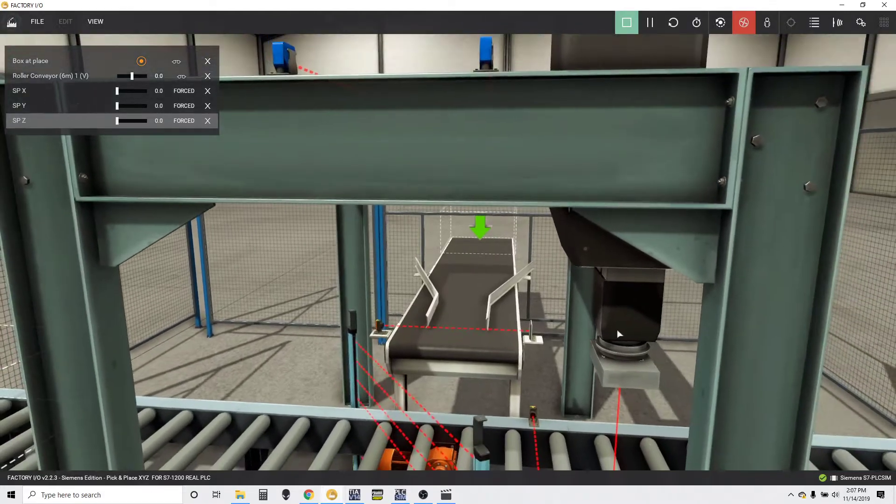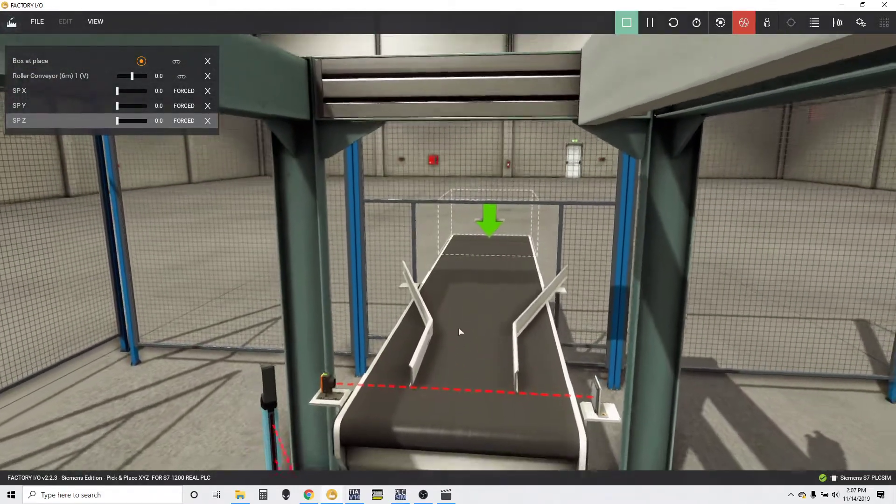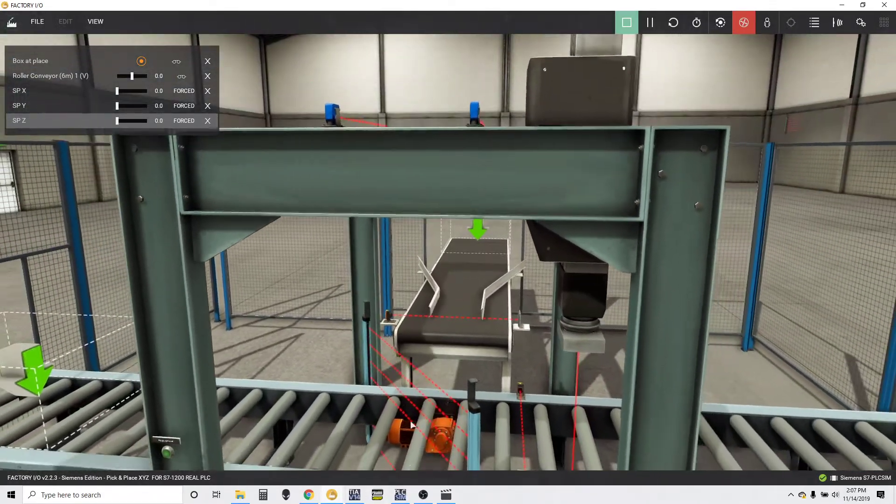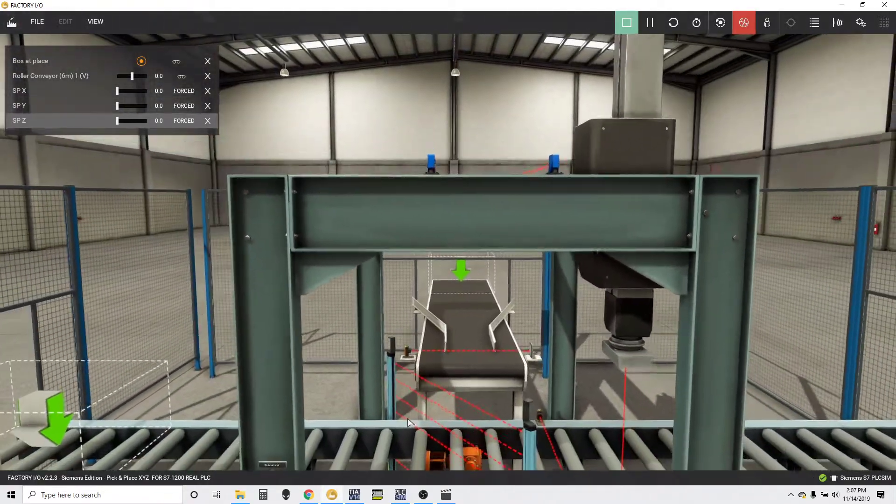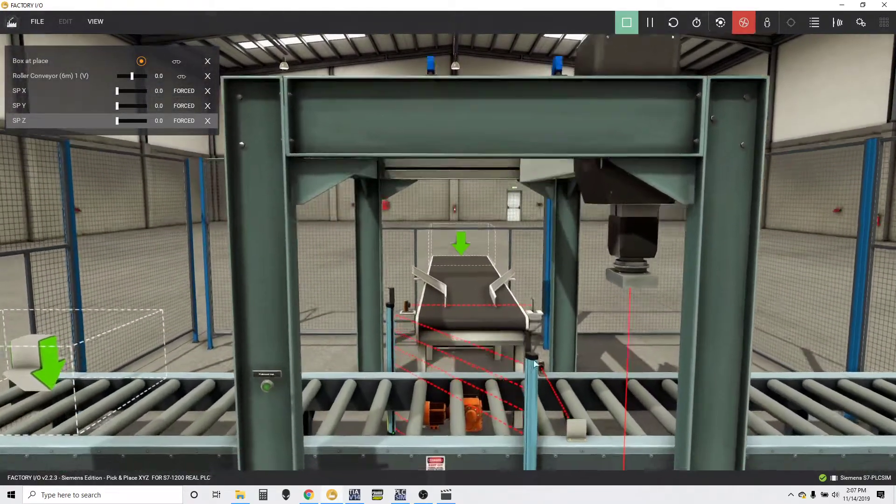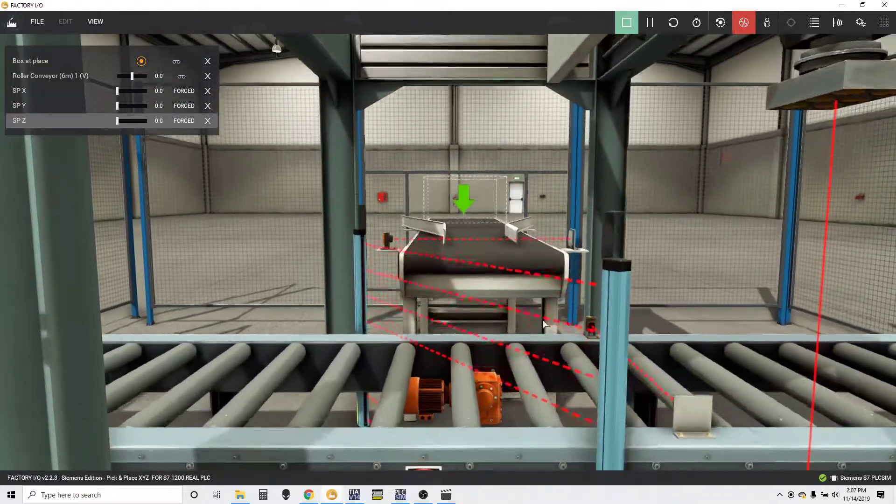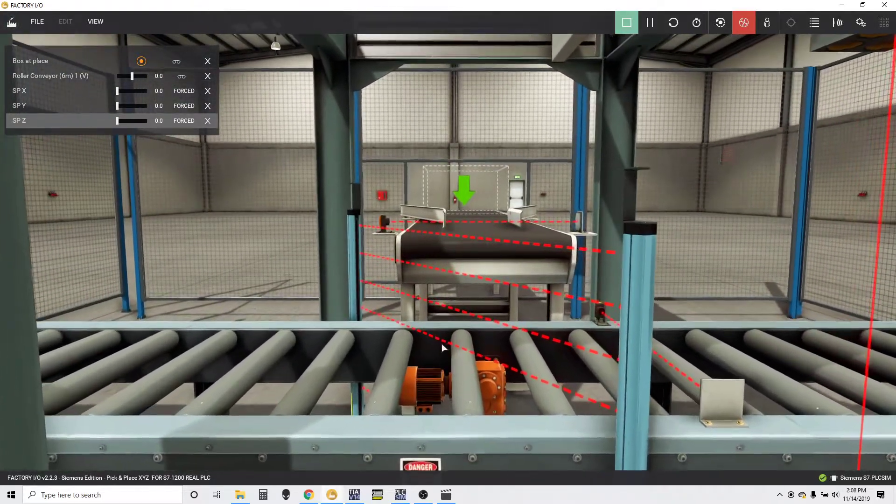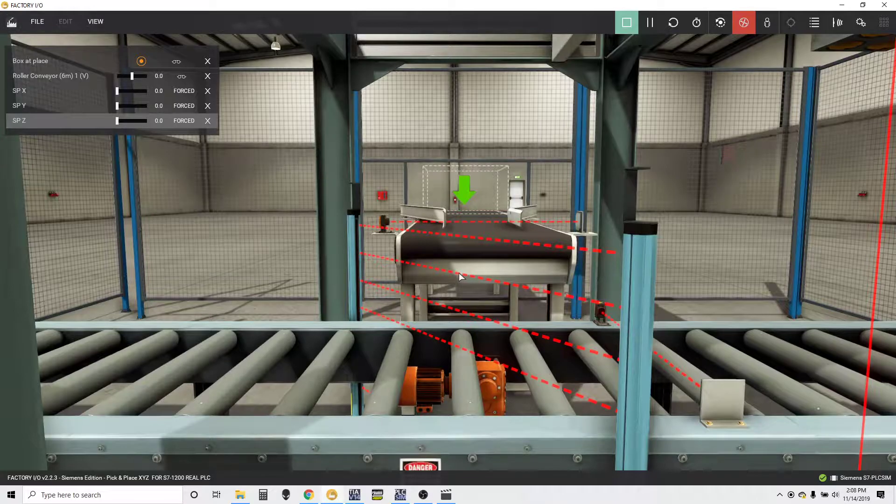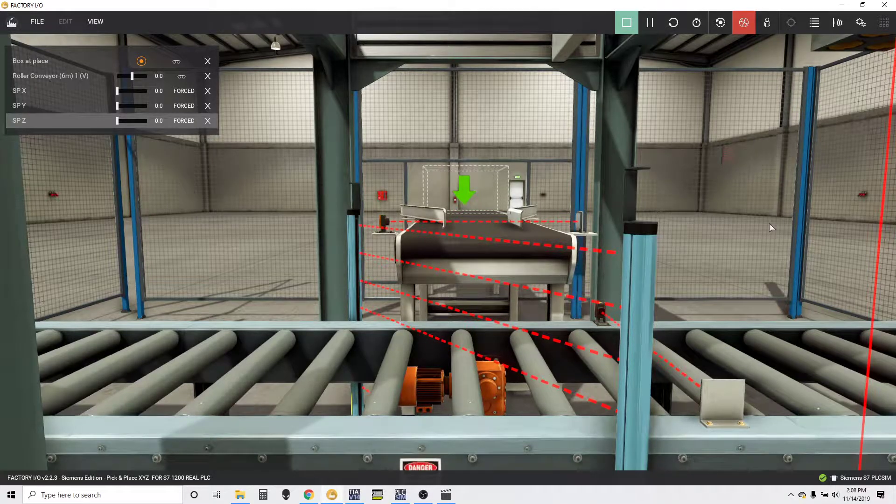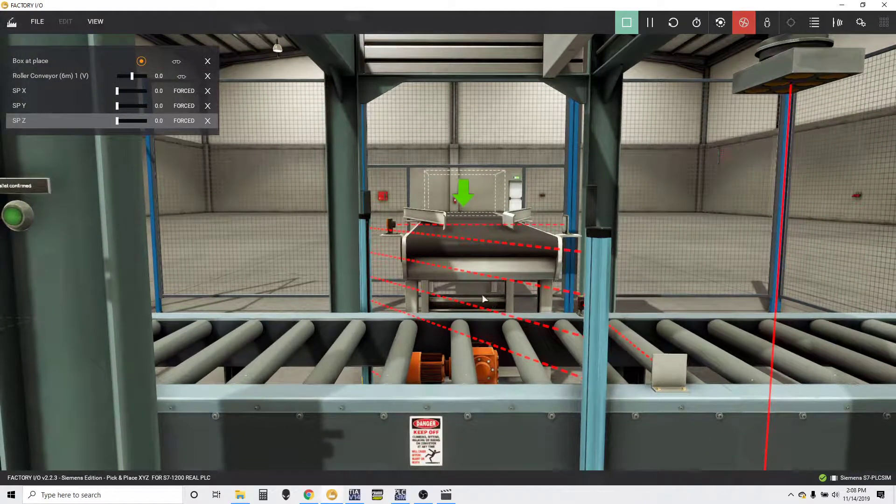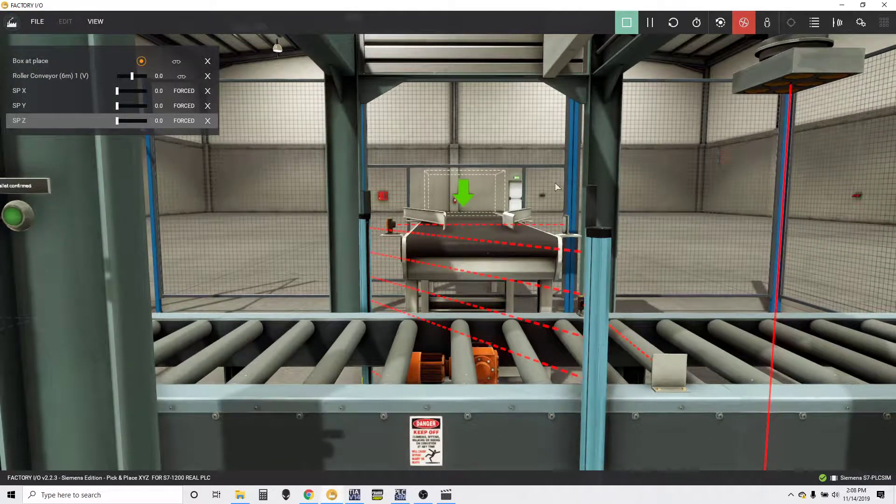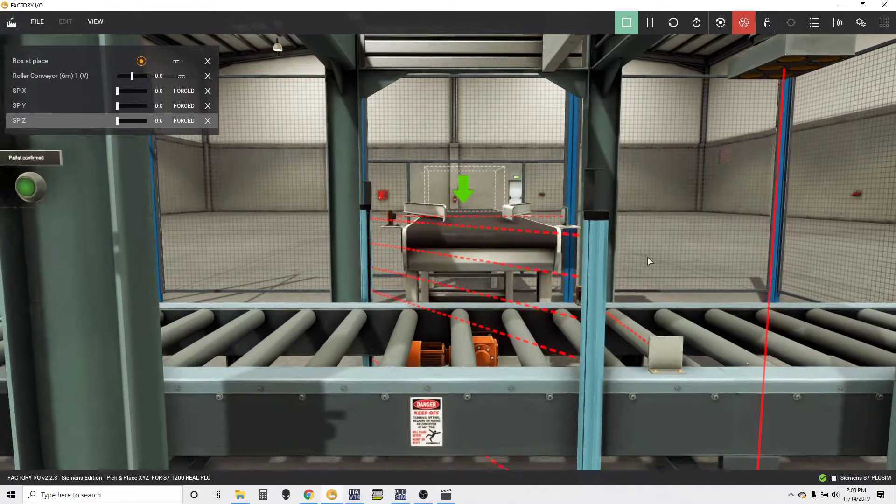robot will go over here and pick the two boxes—one to the left, one to the right. And how it's going to know if you had a box on the pallet is by this emitter sensor over here. It's going to basically break at least three of these sensors. Once you broke three of these, it's going to keep a count.